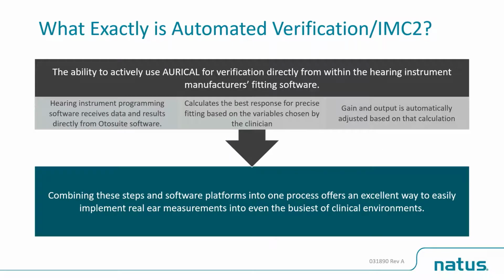So what does that allow you to do with Aurical? It will allow you to open the hearing instrument manufacturer software and do all of the verification right from the Phonak software. When you get done, those results will be stored either in the Phonak software or in the OtoSuite software, so you can view those results wherever you need to. It calculates the best response because you can use proprietary fitting algorithms as well as the NAL or DSL targets. And you can also select the option to do automatic gain and output adjustments based on the information being received.